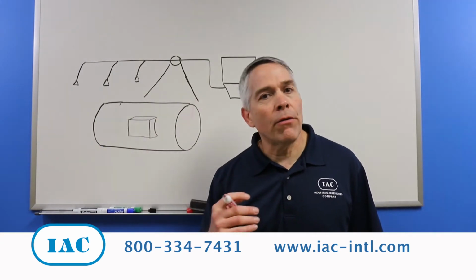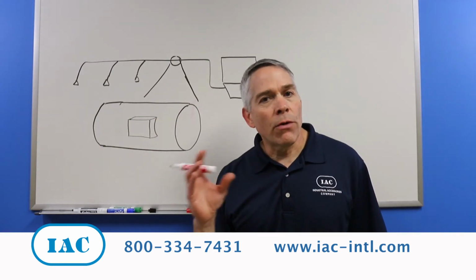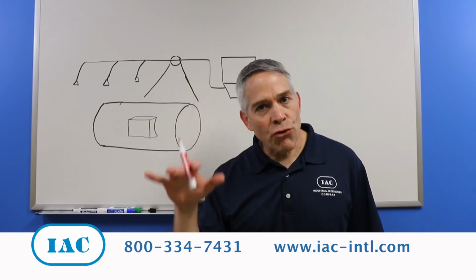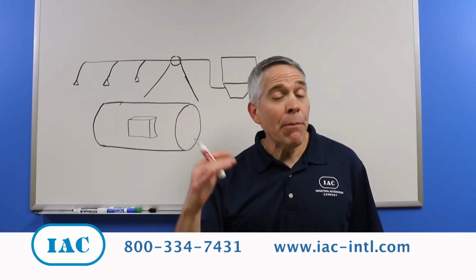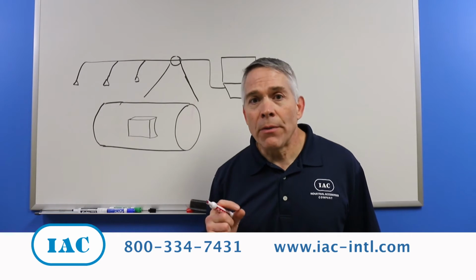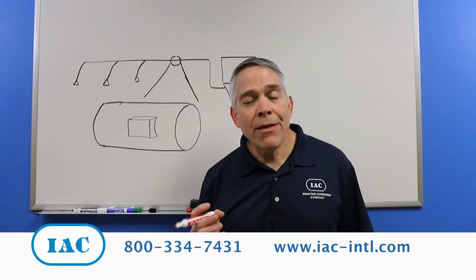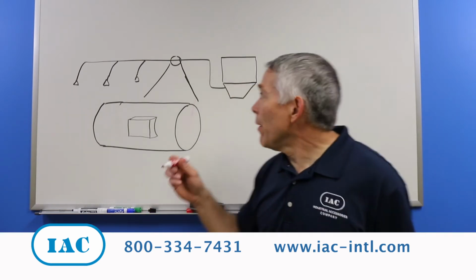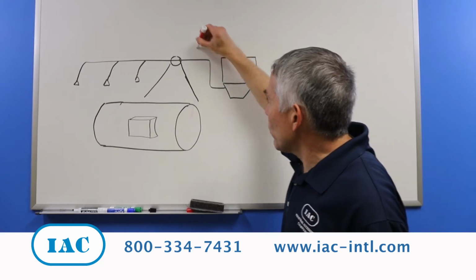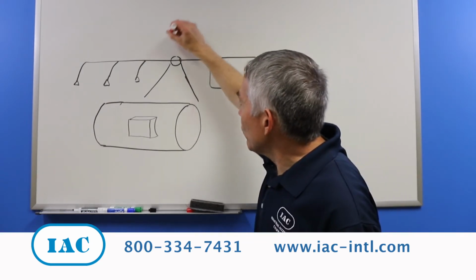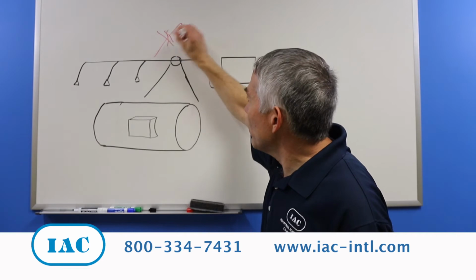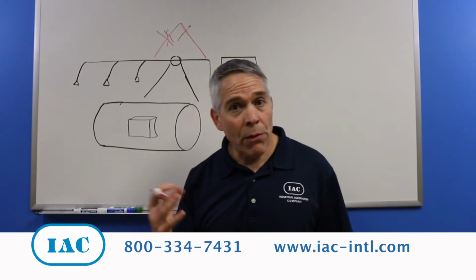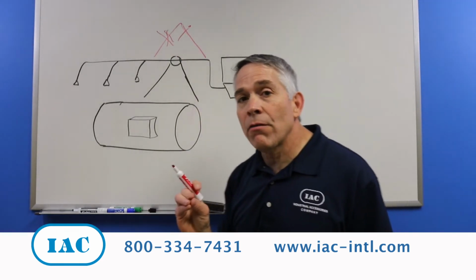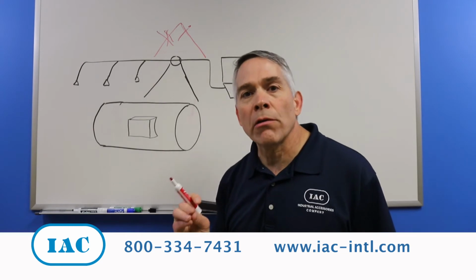Why is that? Because even if we apply the adequate velocities, we're going to have some dropout, and that can build up to become a problem. But then there are many installations where we cannot have an up-and-down design of ductwork to avoid horizontal sections. That cannot be done because of space requirements or the building or whatever. So in many cases, we do need to run horizontal ductwork.